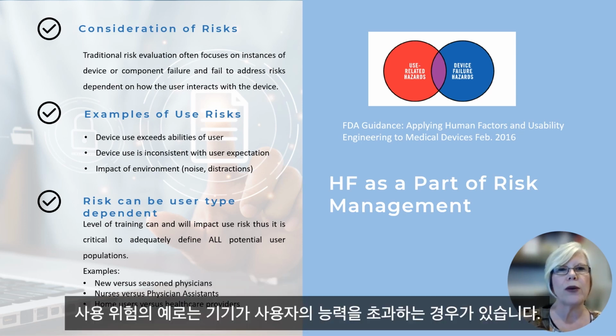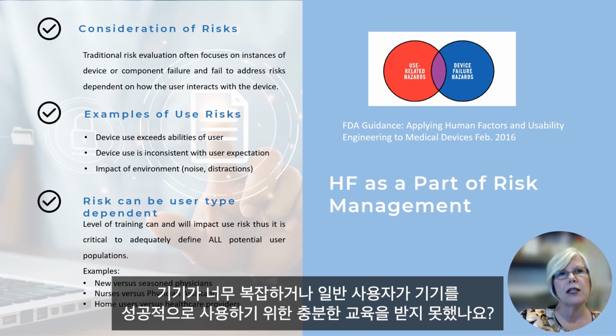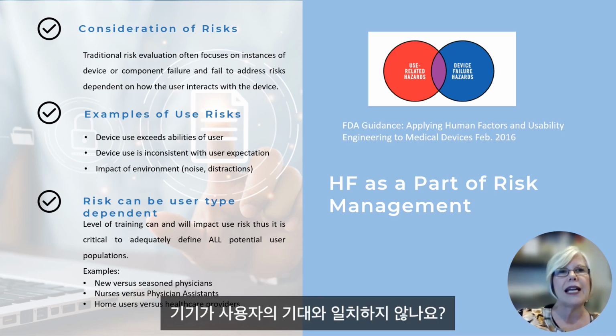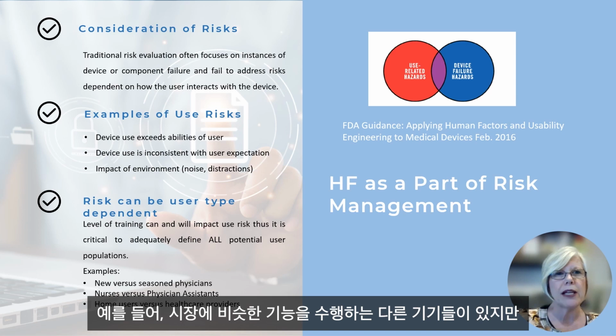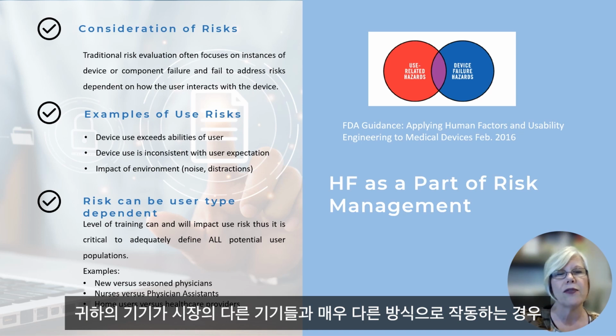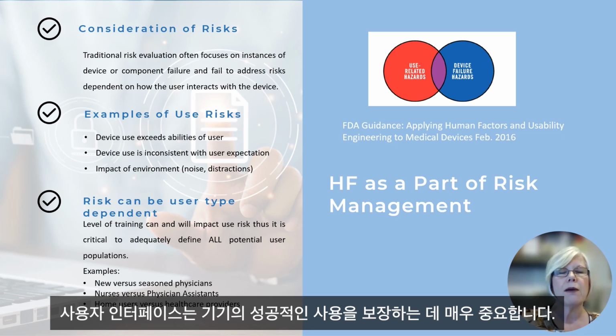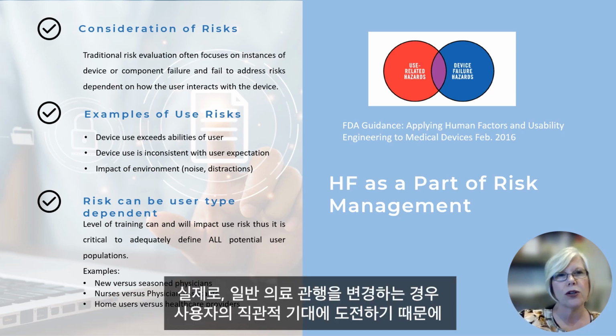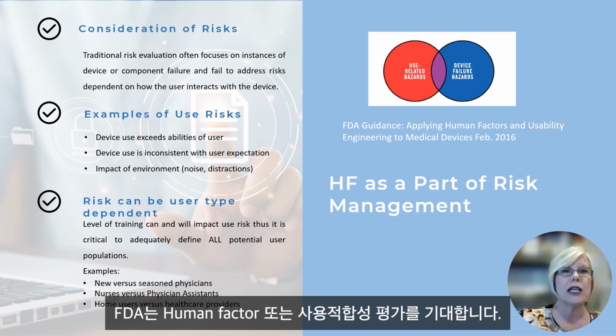Examples of use risk are things like the device exceeds the ability of the user. Is the device too complicated, or does the normal user not have enough training to successfully use the device? Is the device inconsistent with the user's expectation? For example, if there is a similar device on the market that does the same function as your device, but your device works in a very different way than the other devices on the market, the user interface becomes critical to ensure successful use of the device. In fact, FDA expects a human factors or usability study if you're changing the general medical practice, because you're challenging the user's intuitive expectation based on how they've used other devices.